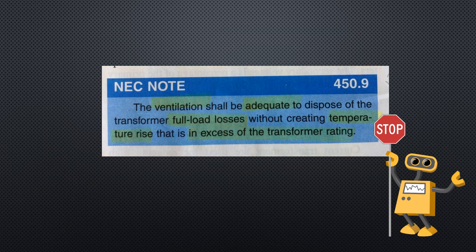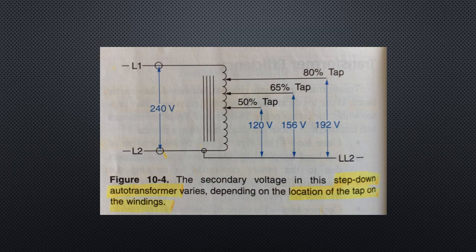NEC Note 450.9: Ventilation shall be adequate to dispose of the transformer full load losses without creating a temperature rise in excess of the transformer rating. Liquid insulated transformers are heavier than comparable dry type transformers. Extra precautions must be taken to check for leaks. Ascarel-filled transformers are no longer used due to environmental hazards and have been replaced with less flammable liquid insulated transformers whose insulating liquid may burn, but flames will not spread from the point of ignition.